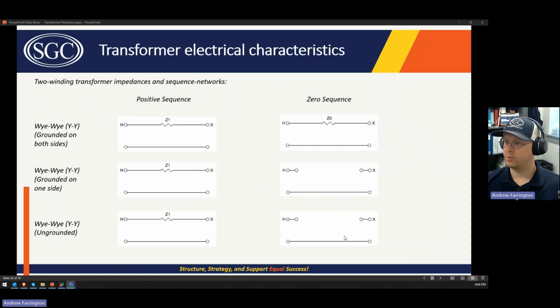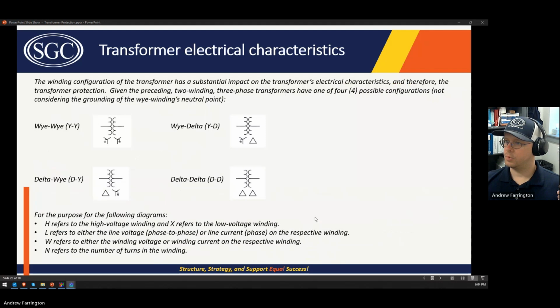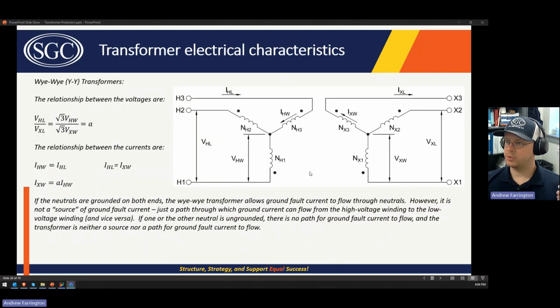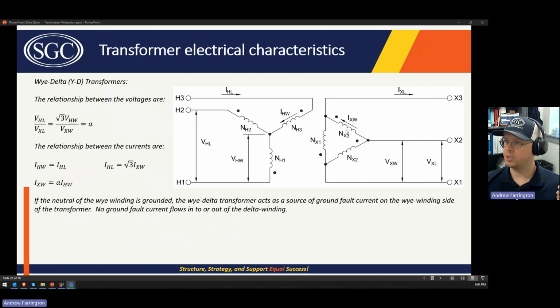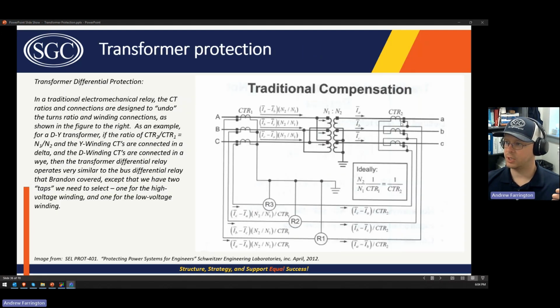So this is just like we went over back here. You know, the current seen for a delta, the current seen by the winding is the square root of 3 higher than the current seen by the phase. So we're undoing that with our delta CT connection. I think others have already covered how that works. So you just want to know that this is going to be the square root of 3 higher than the actual current seen by any individual CT. And again, that has the nice benefit of undoing, quote unquote, the additional phase current seen by the Y side than you would see by the delta side.